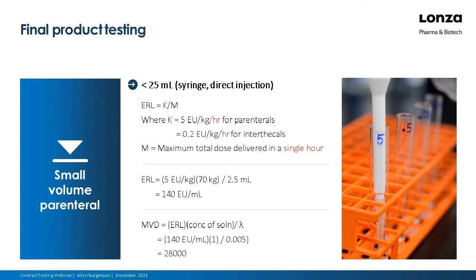So for our small product testing, you have to set your endotoxin release limit. And that is in all of the compendia, established by K/M, where K is the threshold pyrogenic dose for humans, which is 5 endotoxin units per kilogram per hour. And don't forget that per hour in red. And if you're looking at intrathecals, it's 0.2 EU per kilogram per hour. And M is the maximum total dose delivered in a single hour.